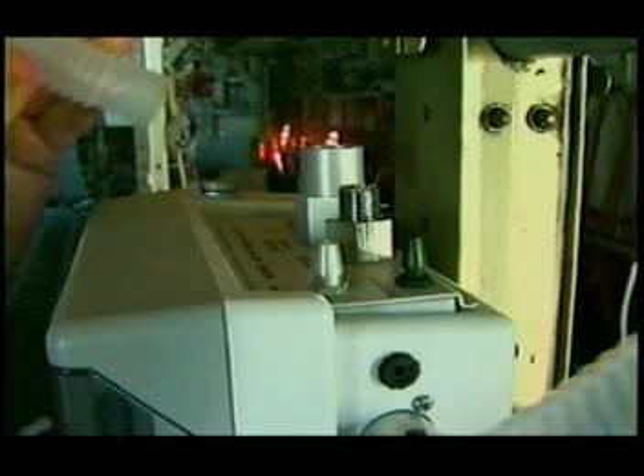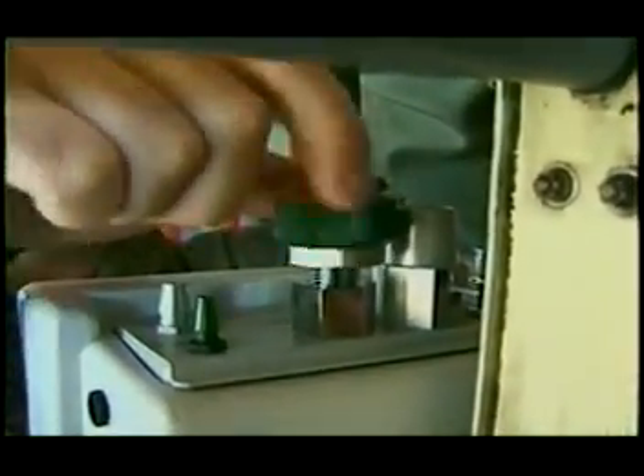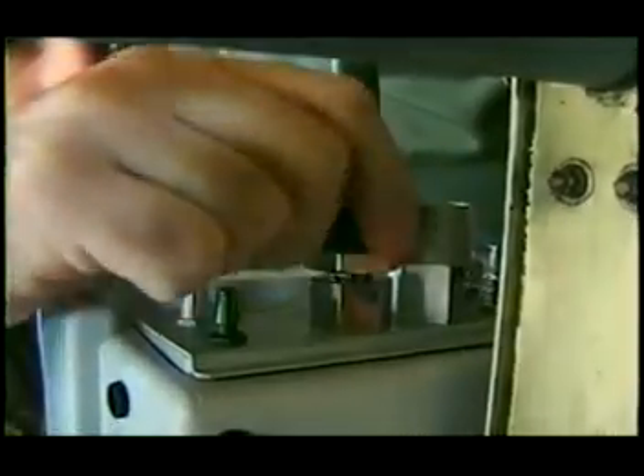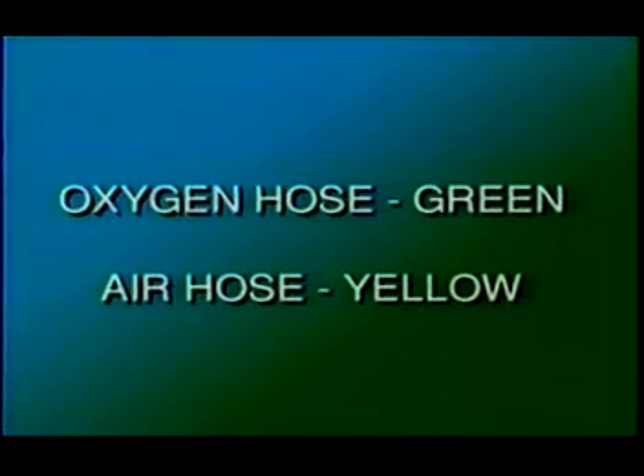Hoses connect to fittings on Eagle's connector panel. Each fitting is labeled. If external 50 psi medical grade gases are used, connect their diameter index safety system, DISS, hoses to the fittings marked oxygen in and air in, respectively. The oxygen hose is color-coded green. The air hose is color-coded yellow.